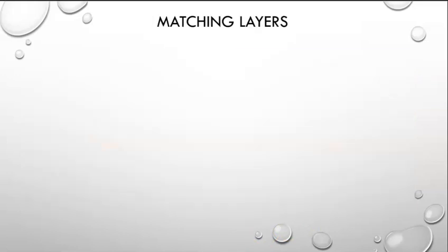So let's talk about this matching layer. This is important because if we think back to our discussion of the interaction of sound and media in Chapter 6, we found that at an interface where there's a difference of impedance, you get a reflection back, depending on the difference of impedances. Well, the impedance of an ultrasound piezoelectric crystal is significantly different from the impedance of a human body. So if we didn't have a matching layer to overcome this difference, we wouldn't get any sound or very little sound into the body.